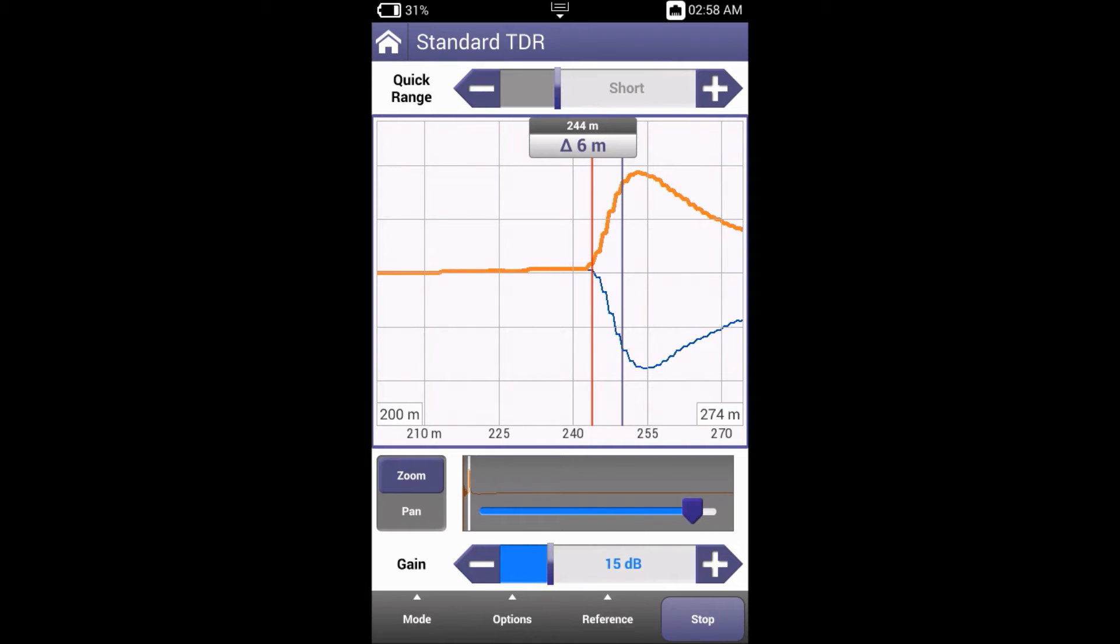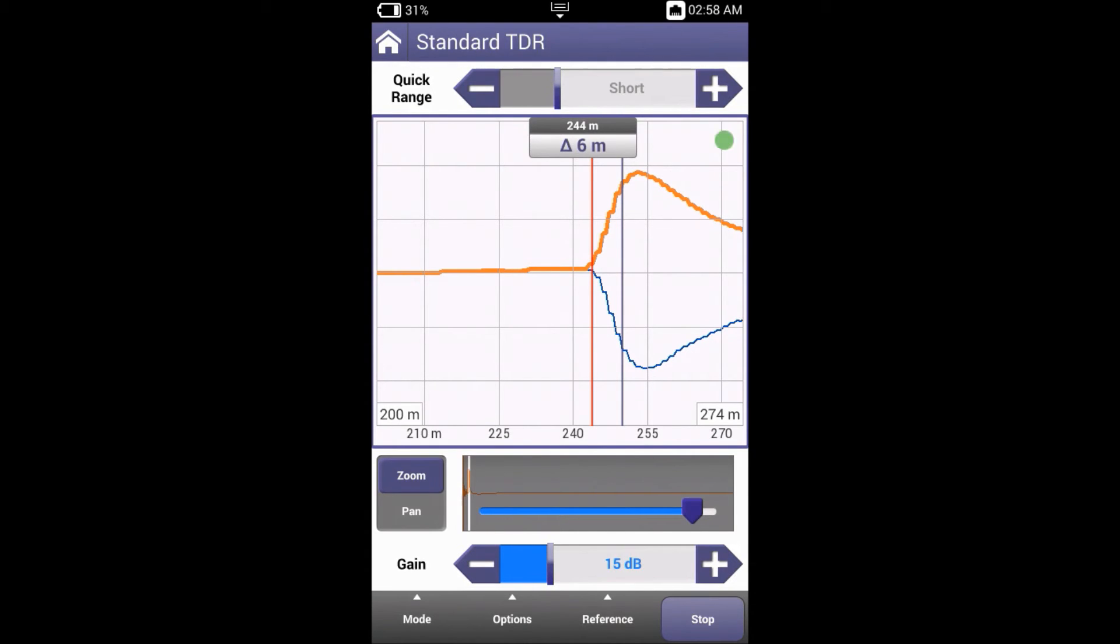The next thing to look at is stress. As previously discussed, HR opens are difficult because the resistance at the fault location increases and decreases. Besides monitoring the trace for changes, another technique is to inject a signal which hopefully disrupts the fault resistance, thereby revealing its location along the trace.